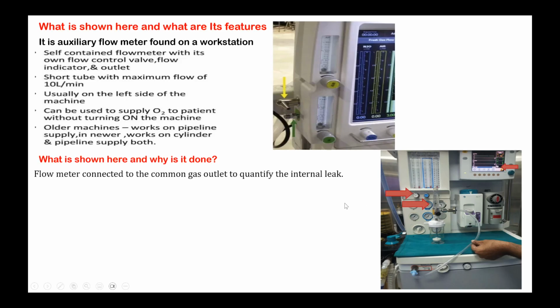Okay, this is to do the internal leak test. This is called the internal leak test. A flow meter connected to the common gas outlet quantifies the internal leak that can happen when all the flow meter tubes are kept in closed position. Okay.